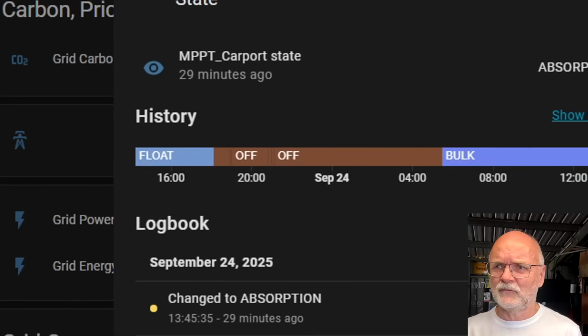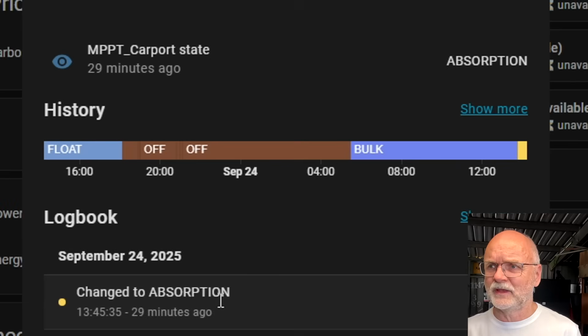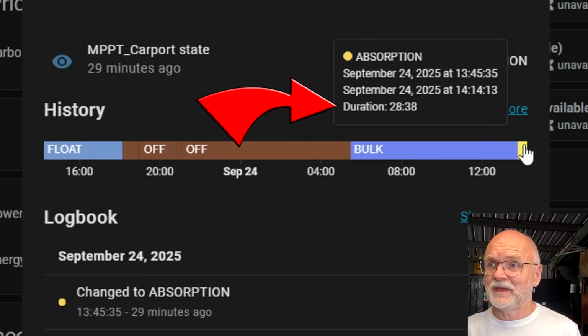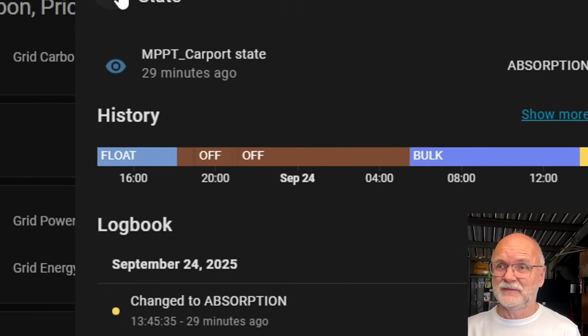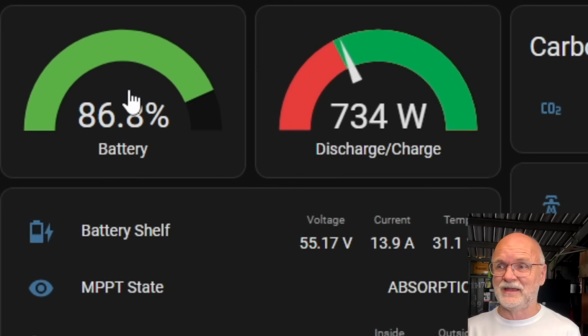So it needs to stay under that, under 17 amps for 3 minutes to reset to 100%. Let's have a look how long we are absorbing already for. 28 minutes only, so we've got another 32 minutes to absorb. That should do the trick, and we should see 100% here then in the display.